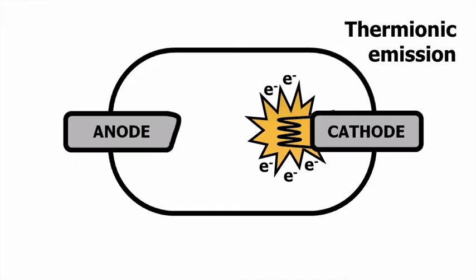A current running through the filament causes it to become extremely hot. So hot that electrons are actually dissociated from the metal and form an electron cloud around the filament. This is kind of like the filament in an incandescent light bulb. A current running through the light filament creates heat, which creates the light. In an x-ray tube, the filament gets so hot it actually creates free electrons.